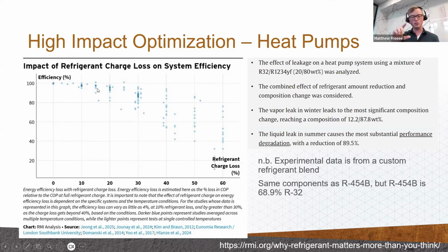And not only that, because we put these heat pumps in different operating conditions, leaks at different operating conditions and at different times of year, especially if you're looking at air source heat pumps, are actually going to leak different component parts. So the refrigerant doesn't leak as an even mixture. As it's leaking, the refrigerant composition changes and the refrigerant performance changes.